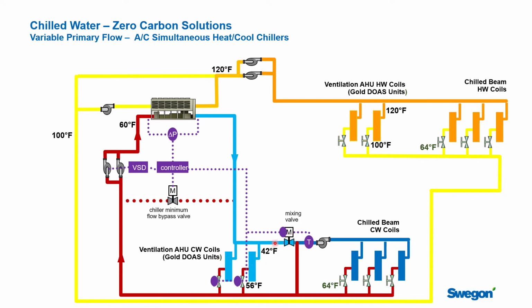We use a mixing valve in here to run a secondary loop at 57 degrees out to the chilled beams. And so this loop, we're adding energy from the building into it. So we now have a low-grade energy source of 60-degree water. And if we had some heating load somewhere in the building, maybe more in the fall, the refrigeration plant in here would extract the heat from this loop, and rather than rejecting it to atmosphere, would actually use it to heat the hot water loop.